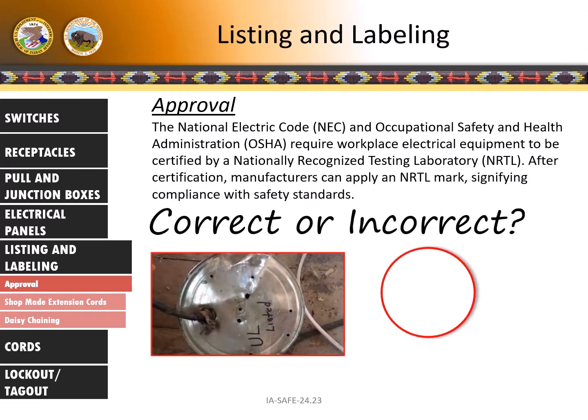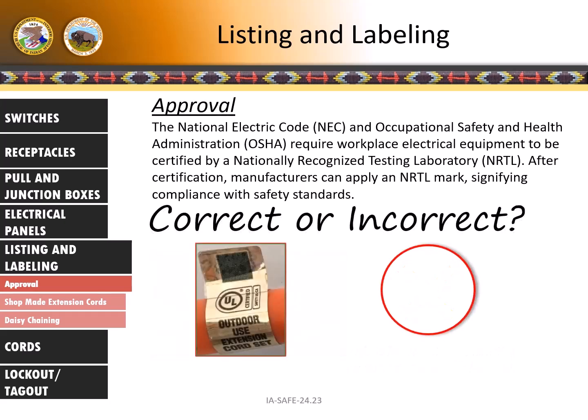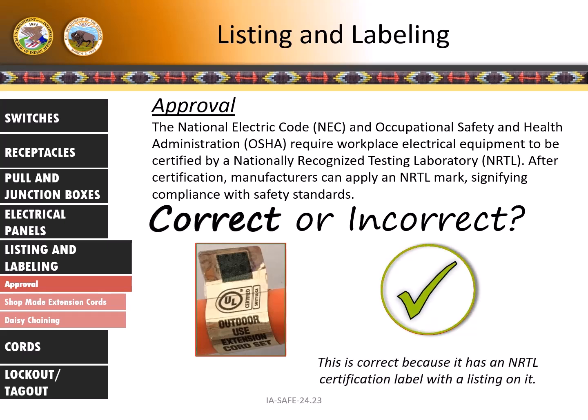Is this example correct or incorrect? This is incorrect because the cover is not listed or labeled. Is this correct or incorrect? This is correct because it has an NRTL certification label with a listing on it.